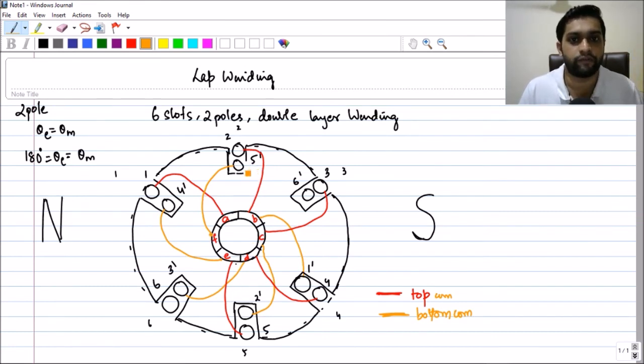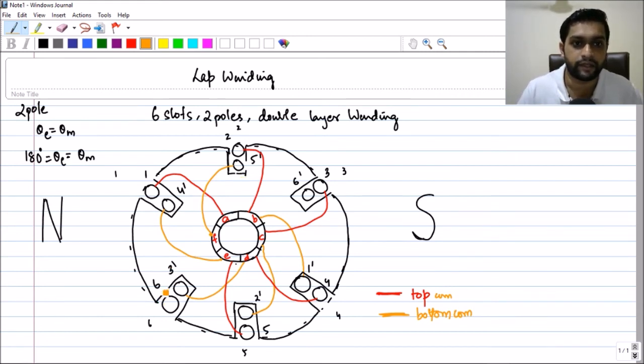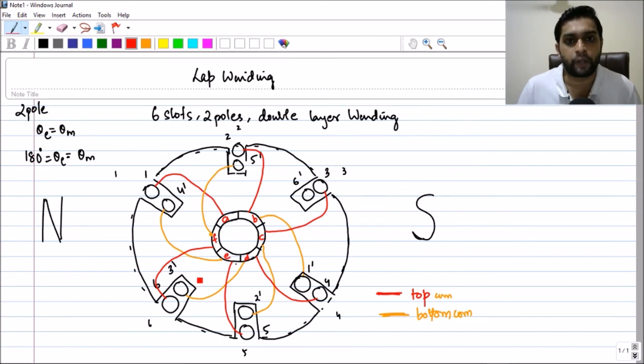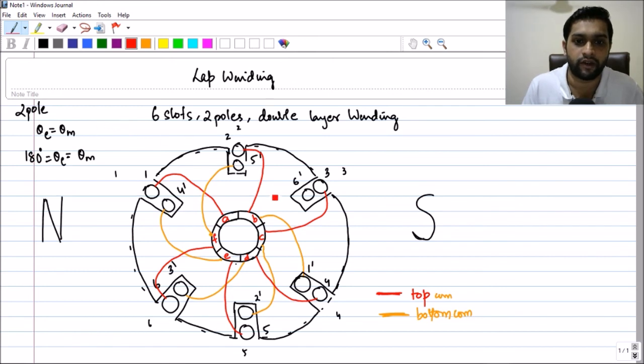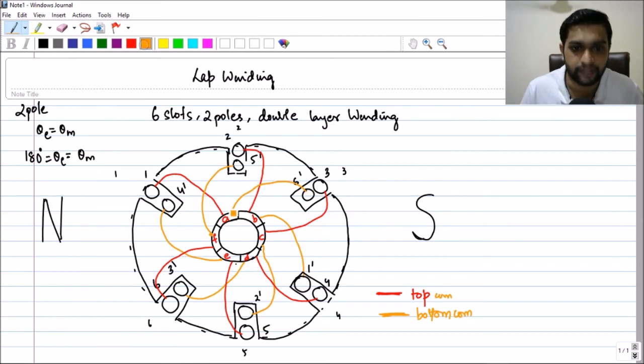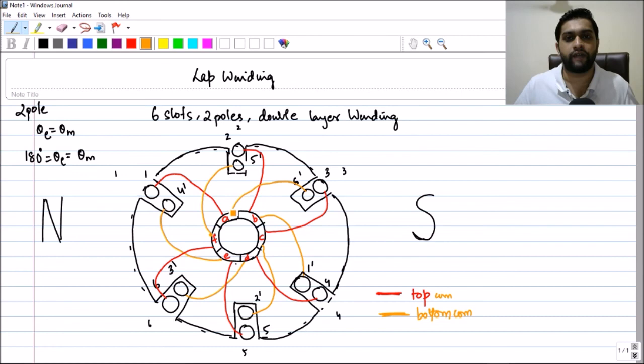Five-dash, the end of coil five, gets connected to the start of the next coil — the top of coil number six. Finally, because lap winding is a closed winding, the last connection is between six-dash and coil number one. It comes back and connects, closing the winding.